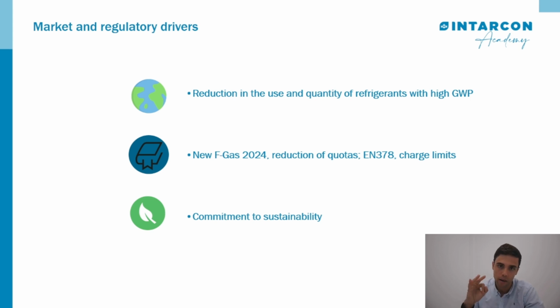The main market and regulatory drivers are three. The first one, reduction in the use of refrigerant with high GWP, because current and future regulations are progressively limiting the use of gases with high global impact. So mainly we are forced toward solutions with natural refrigerants such as propane. Next, F-gas 2024 regulation and specific regulations such as EN 378 with a charge limit. These restrictions are being timed with a reduction in HFC marketing quota. So the new requirements are very tight with the refrigerant charge in installations.